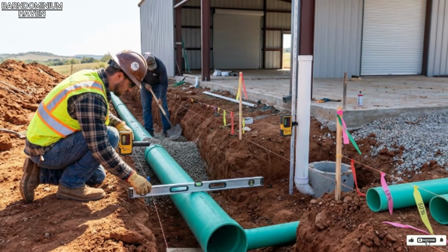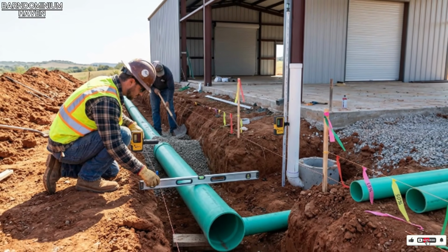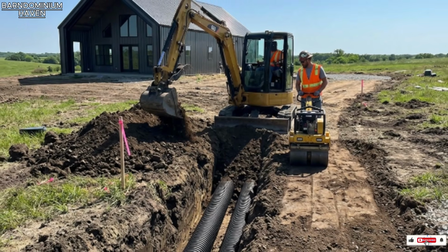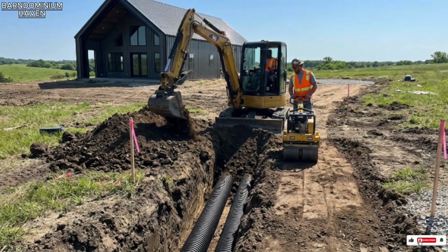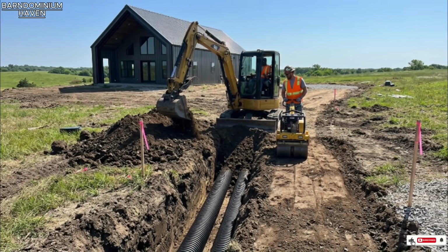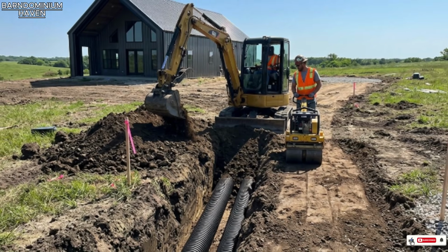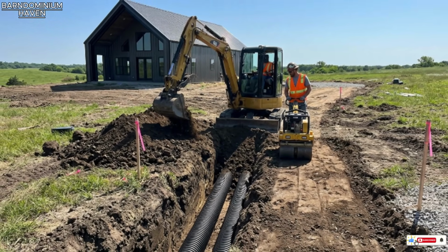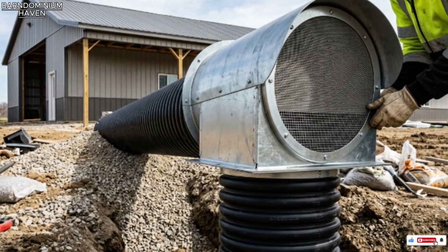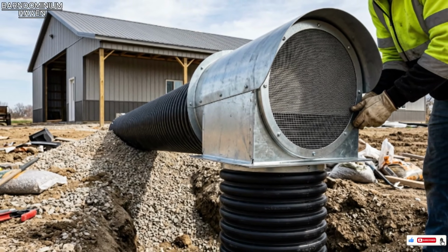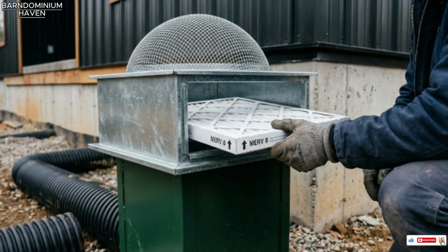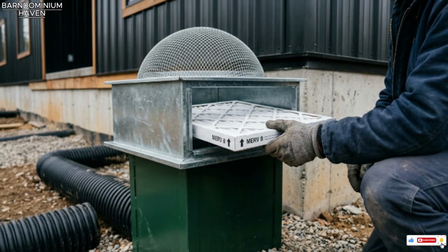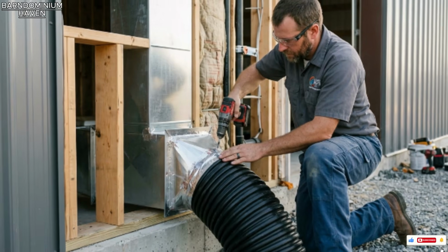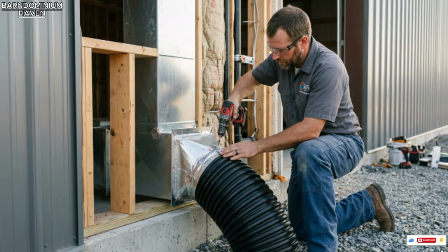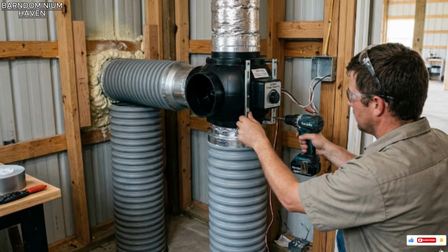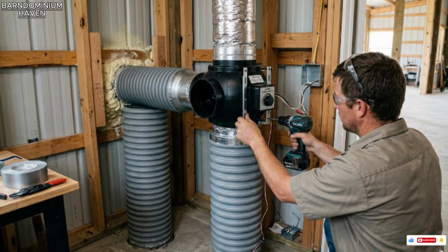Pipe installation, bedding material, pipe laying, slope verification, backfill compaction, $1,200 to $2,400. The pipe must be installed with a continuous slope toward a condensate drain. Earth tubes produce condensation as warm humid air contacts the cool pipe surface. And that condensate must be drained away from the building rather than allowed to pool inside the pipe. Intake structure, screened intake housing with insect and rodent exclusion, pre-filter, positioned at the far end of the pipe run, $400 to $800. Building integration, connecting the earth tube to the building's air distribution system, installing the supply fan, connecting controls, $1,500 to $3,000.